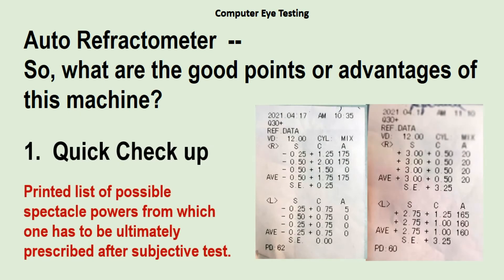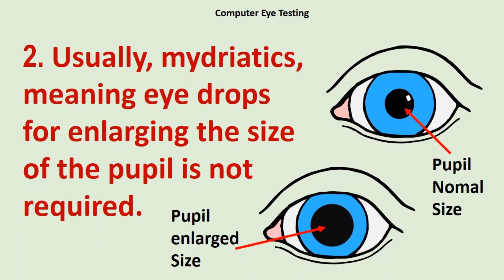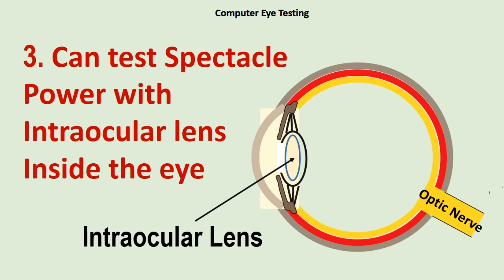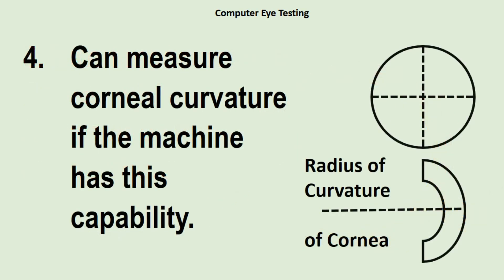So what are the good points of this machine? Number one: it gives very quickly a printed list of possible spectacle powers, from which one has to be ultimately prescribed after subjective confirmation with the patient. Number two: usually mydriatics — eye drops for enlarging the pupil — are not required. Number three: it can test spectacle power with an intraocular lens inside the eye. Number four: it can measure corneal curvature, if the machine has this capability.